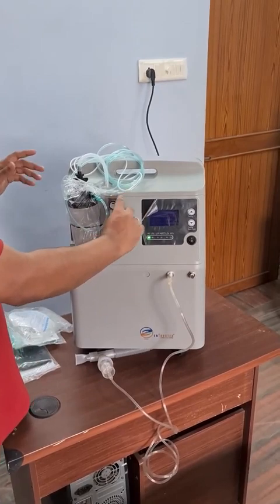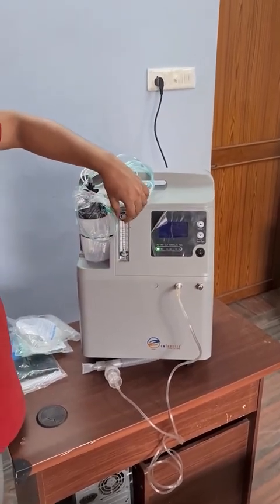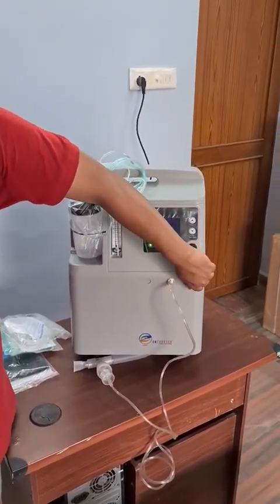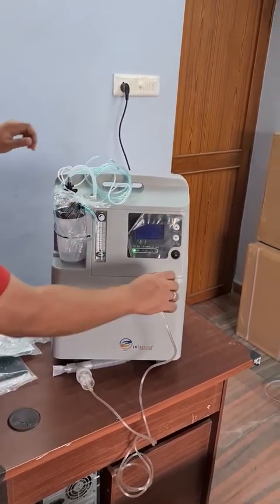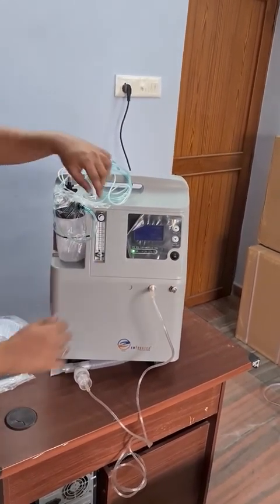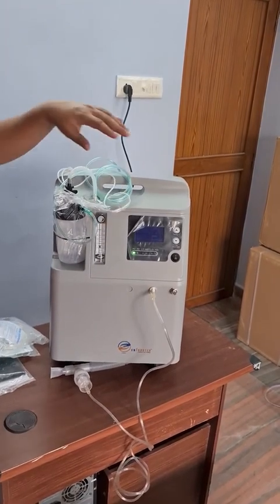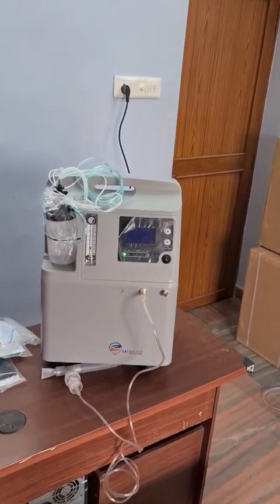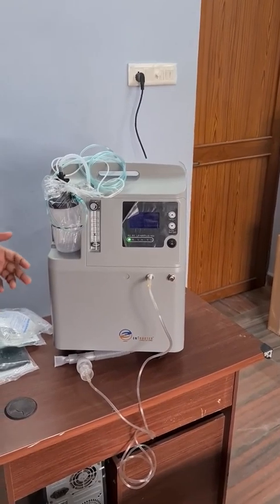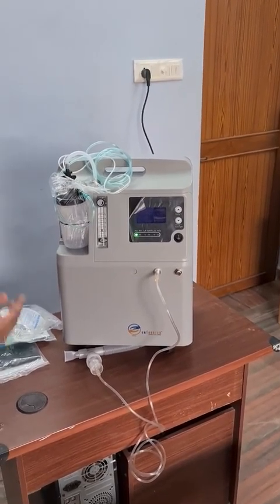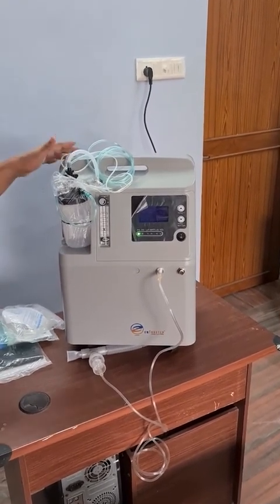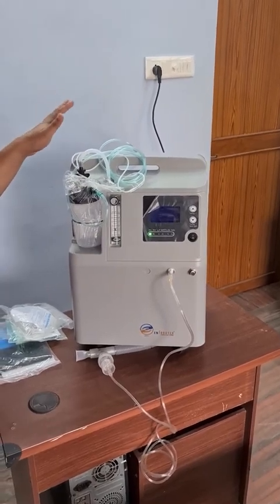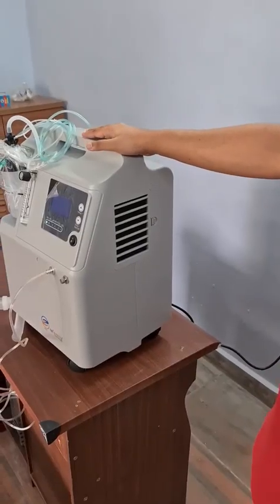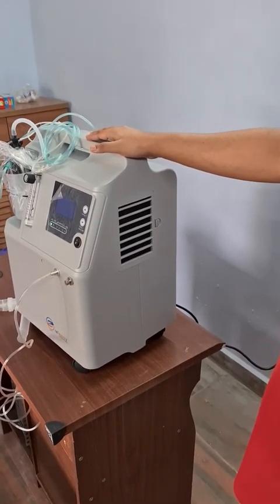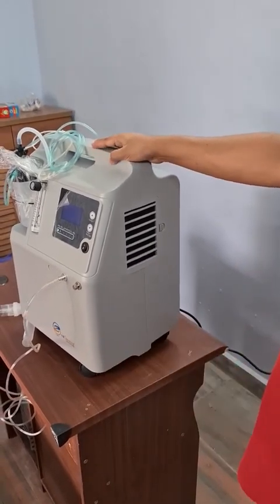When you are going to use the nebulizer, you are going to bring this to 0 and you are going to switch on the nebulization. And after the nebulization is done, bring the nebulizer to 0 and increase the oxygen flow rate. So this is the standard practice. Now the next part, I am going to tell you how to replace the filters and what maintenance is required so that the lifetime of the device comes for a longer time. I'm going to show you how to replace the filters and what maintenance to do for the concentrator.